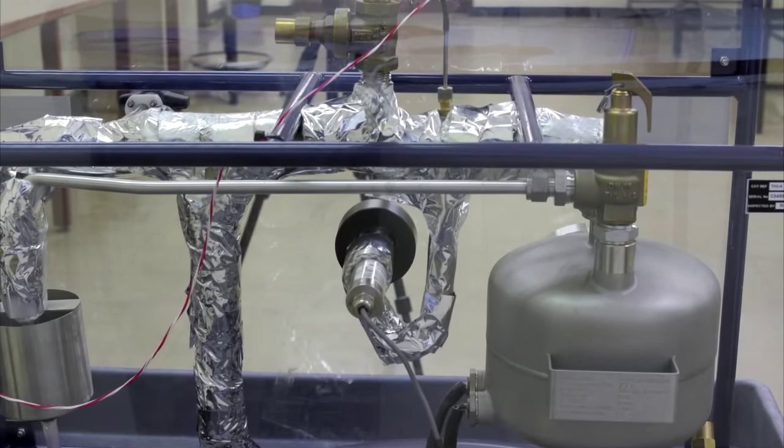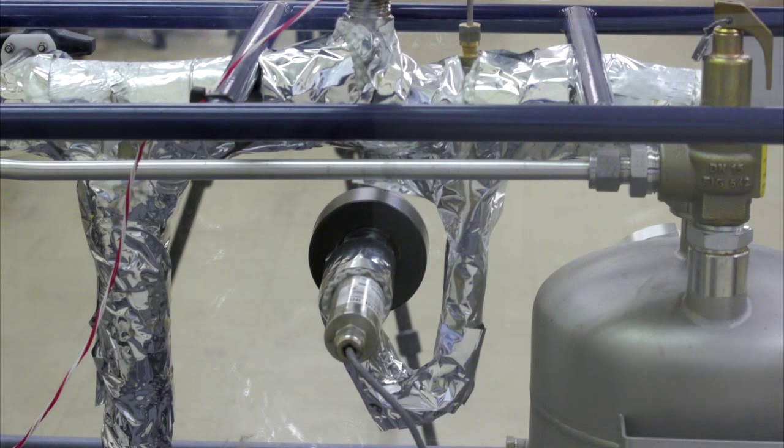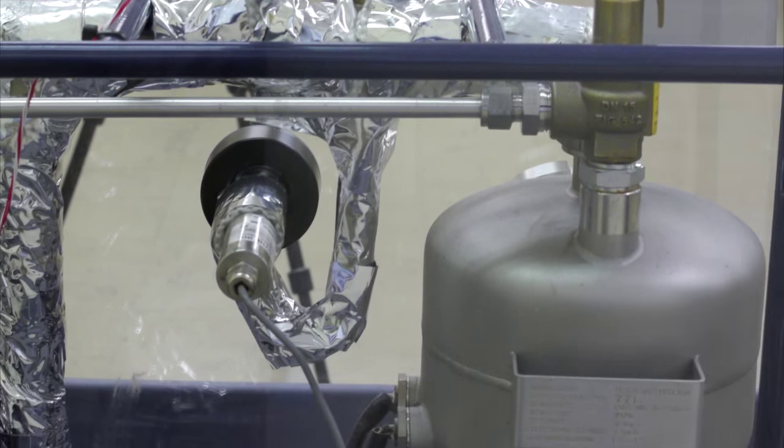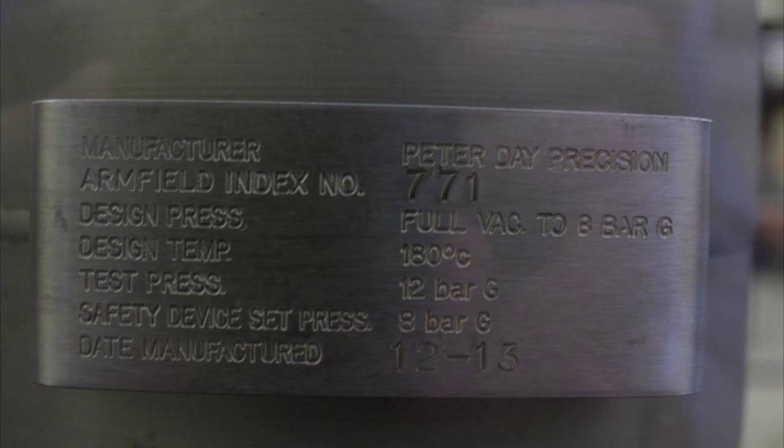Behind the bourdon gauge is a pressure sensor, which supplies a digital reading of the gauge pressure to the control box. The boiler plate indicates that a pressure relief valve will open automatically if boiler pressure ever exceeds 8 bar gauge.